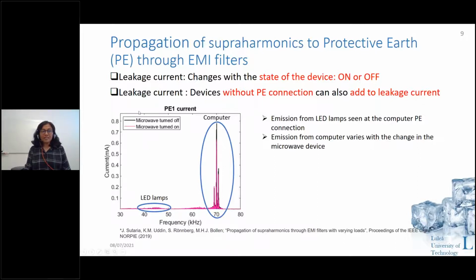Some of the leakage current changes with the state of the device, whether it is turned on or off. If the device is off, it is not generating leakage current. But if there is any other device connected to the same phase as your device, even when your device is turned off, the emissions from that device can propagate through it to the leakage to the protective earth. So they basically propagate amongst themselves, and it changes according to the state of a device.